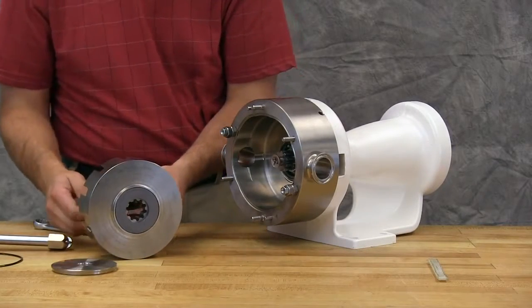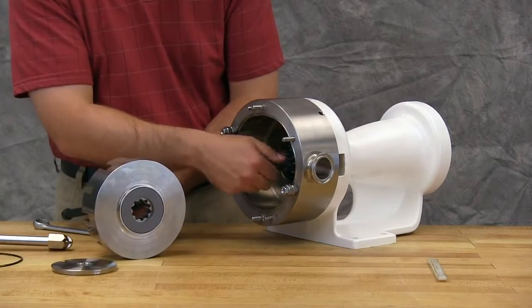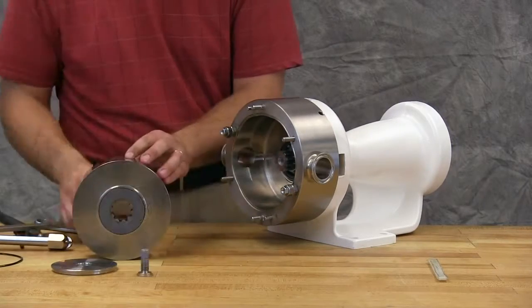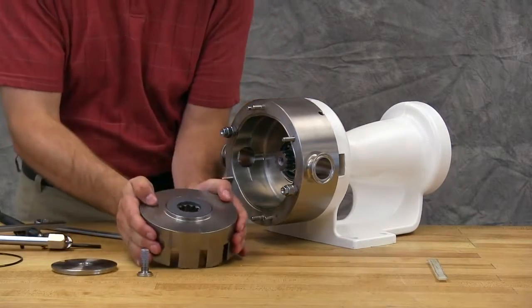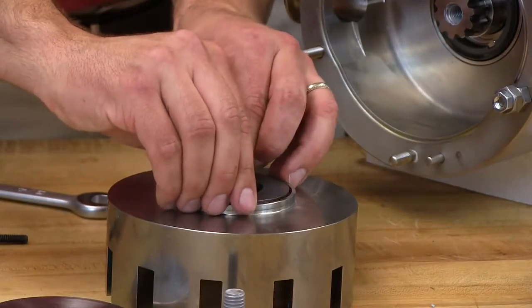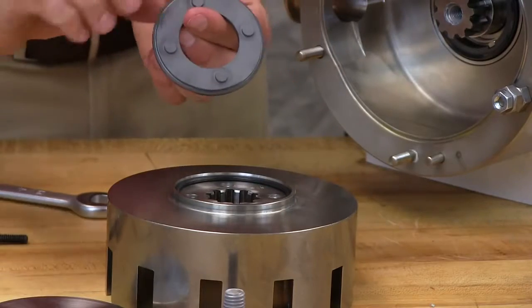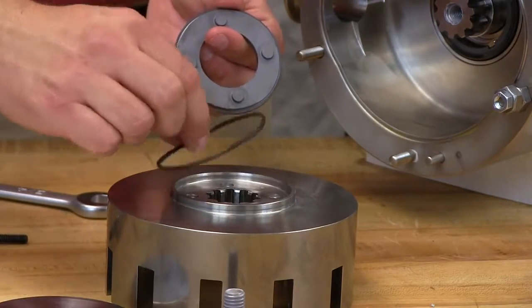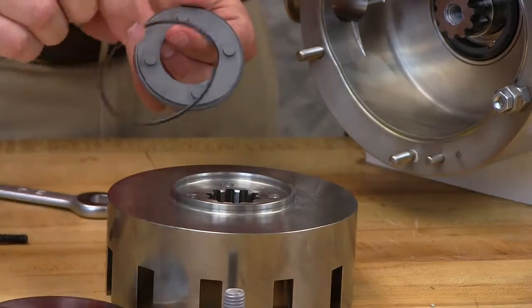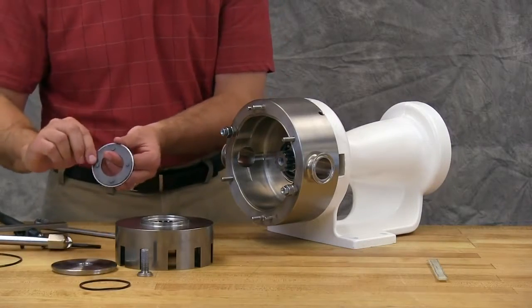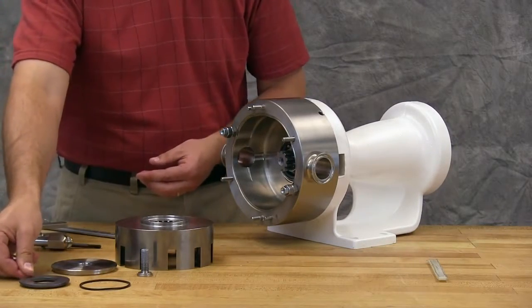Remove the rotor retainer after the rotor has been removed. Remove the mechanical seal rotary member after the rotor has been removed from the casing. Remove the rotary face O-ring. When setting down the rotary face, ensure the sealing surface is facing up.